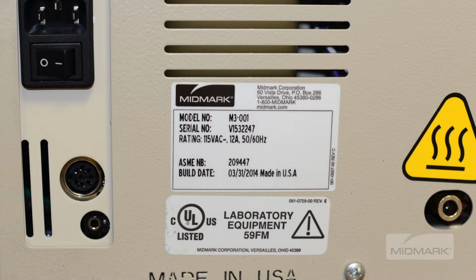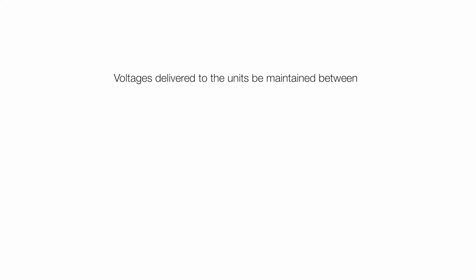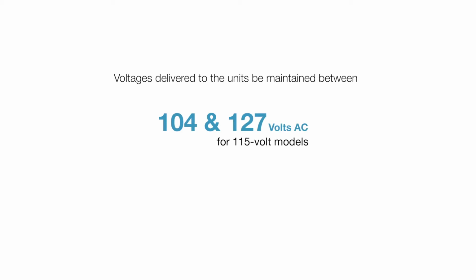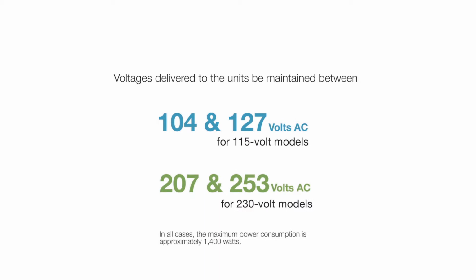The M3 is available in either 115-volt or 230-volt AC configurations. It's critical that the voltages delivered to the unit be maintained between 104 and 127 volts AC for 115-volt models, and between 207 and 253 volts AC for the 230-volt models. In all cases, the maximum power consumption is approximately 1,400 watts.